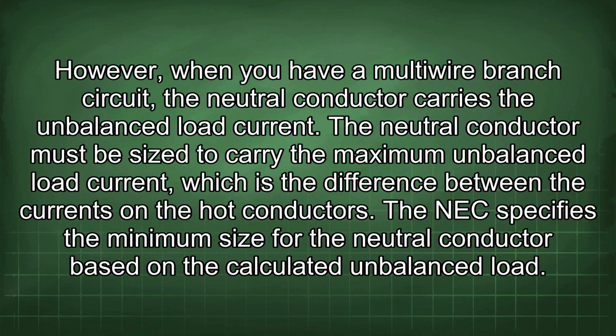However, when you have a multi-wire branch circuit, the neutral conductor carries the unbalanced load current. The neutral conductor must be sized to carry the maximum unbalanced load current, which is the difference between the currents in the hot conductors. The NEC specifies the minimum size for the neutral conductor based on the calculated unbalanced load.